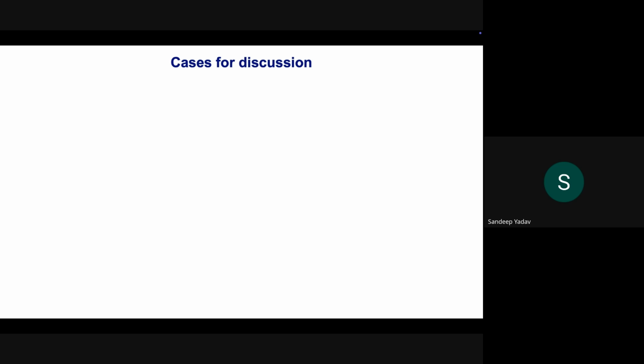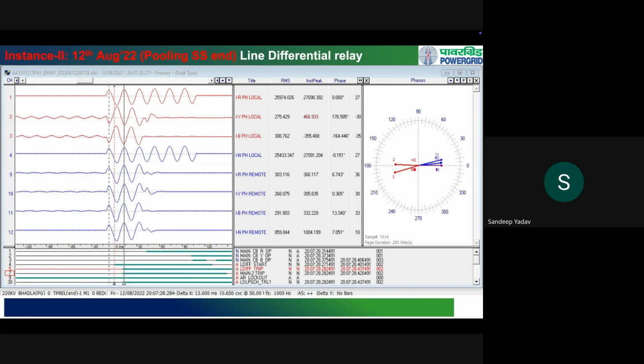Okay, so now these real life incidents corroborate the theory of fault behavior when it comes to the difference between a synchronous source and a non-conventional or non-synchronous source. So the characteristic of the IBR plants or the non-synchronous sources is that the fault currents are not very high. They are more or less limited to their rated values, and the type of current, whether it will be positive sequence or zero sequence, will depend upon what kind of fault there is. So for a phase-to-phase fault, it is largely positive sequence, and for phase to ground faults, it is only zero sequence. There is no negative sequence current contribution from the IBR sources. That is what we have established so far.